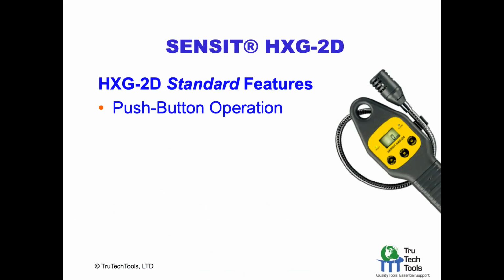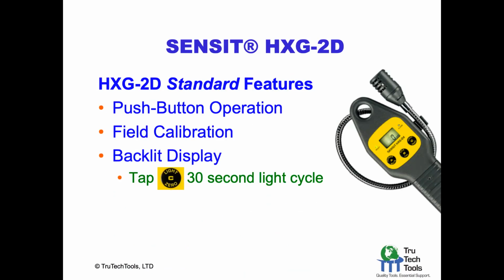So features include push button operation, which we talked about already. It is field calibratable. That means you can get a calibration kit, install it, and you can readjust it to give you that digital accuracy of the display. It's not a complicated process. We also do it at TruTech if you're interested. It's something that you can do yourself, or you can send to us or back to the manufacturer for calibration. Calibration interval usually recommended is 1 year.